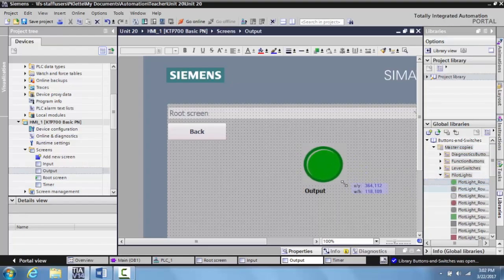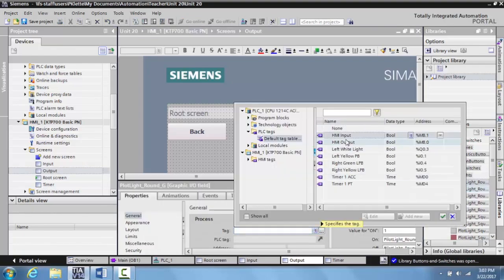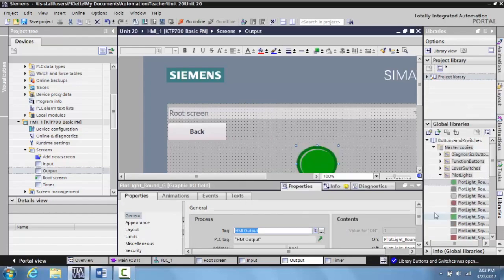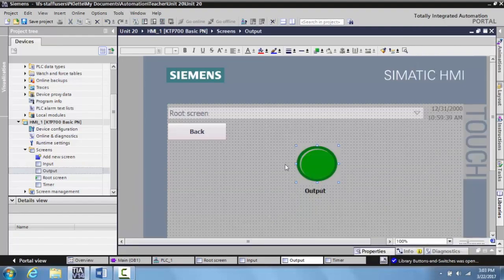Now that's done, we can minimize this. We're doing a very basic setup here – we want to put an output in here, so we'll go to libraries and grab a pilot light. Make it a little bigger and easier to see. Double-click on the properties, bring up our tags, go to the HMI output that we created, select that, and minimize. Now our output data table is set.